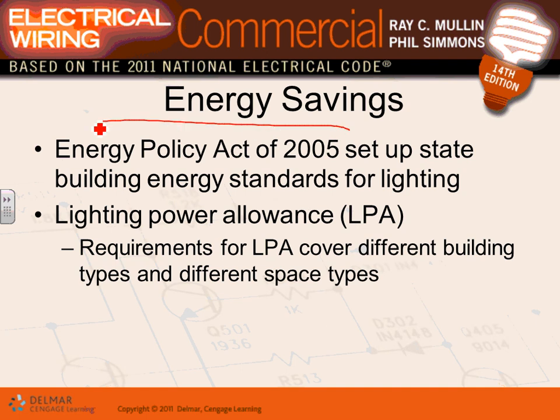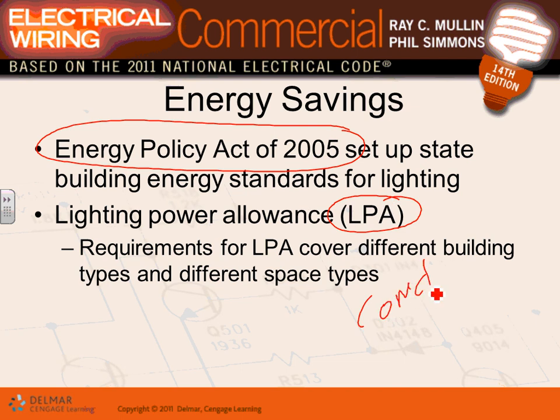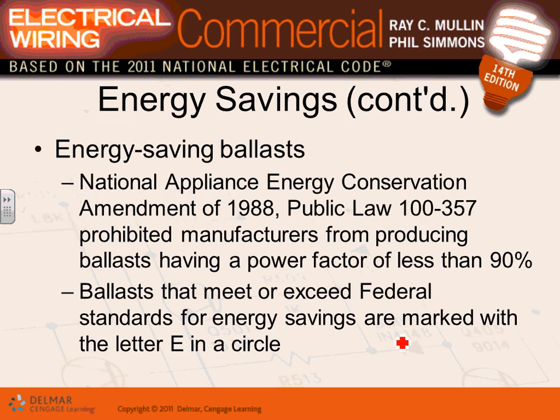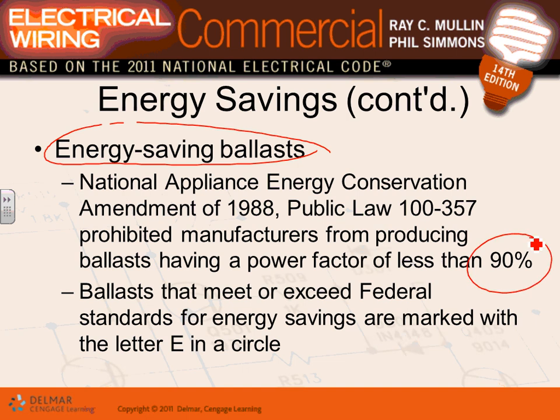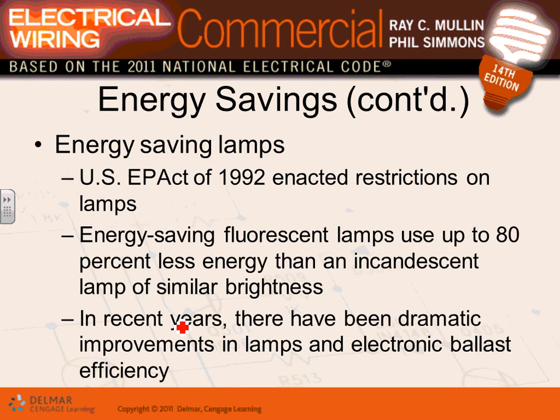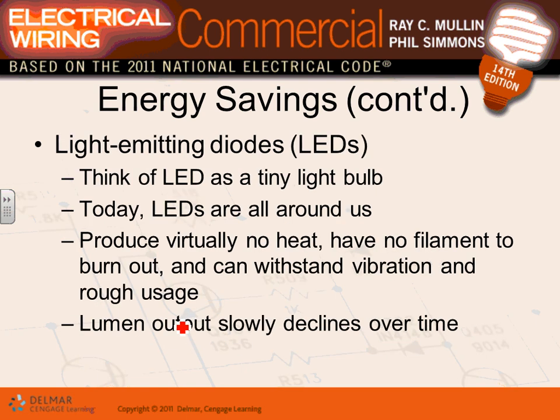The Energy Policy Act of 2005 means all your lighting equipment has to meet building energy standards for lighting — building power allowances. That's what comcheck is for: to meet the energy code. You can't install a lighting fixture that doesn't meet energy code. Ballasts must also be energy-saving and achieve 90% power factor. If they meet or exceed federal standards, they receive an 'E' designation. All these changes — up to 80% improvement in electric efficiency — are because of energy-saving requirements.